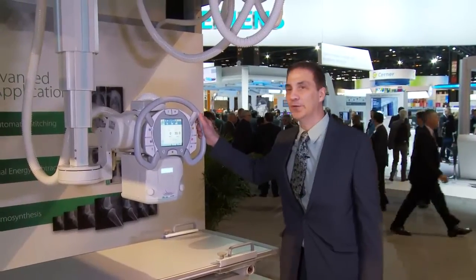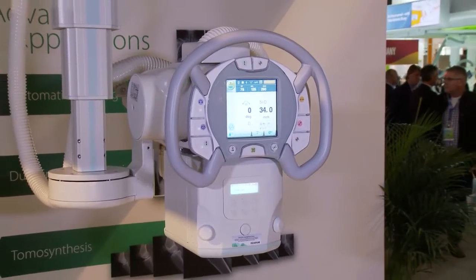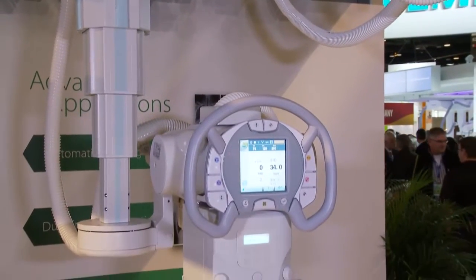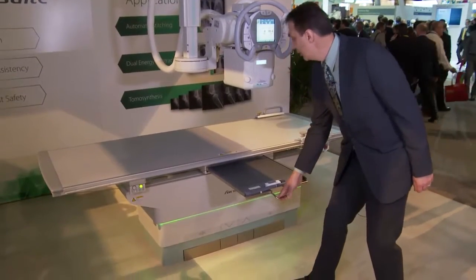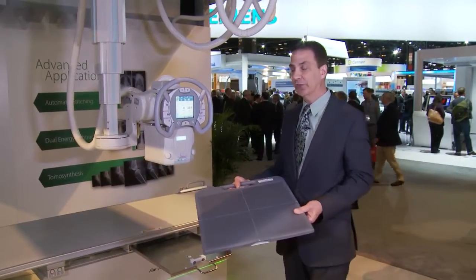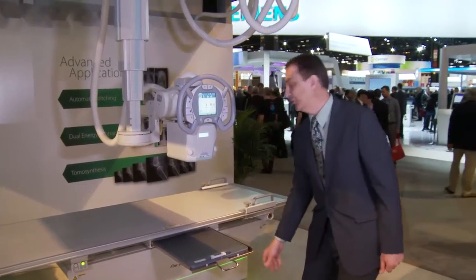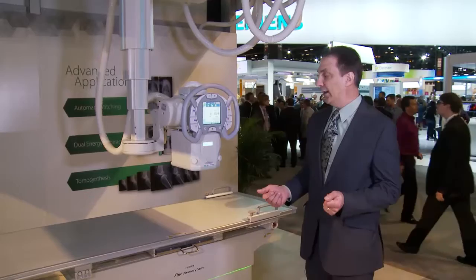Today I'd like to show you our brand new Visionary Suite. This is our high-end room with auto-positioning and advanced application capabilities — a completely new room from Fujifilm. It has tube head controls for your x-ray settings, automatic positioning of the tube head and upright bucky or table bucky, based on the exam menu selected at the workstation. The system features our brand new D-EVO advanced detectors, specially designed for high-speed image capture for advanced applications such as energy subtraction and tomosynthesis. These detectors are now removable, so you can use them for cross-table exams and wheelchair exams.